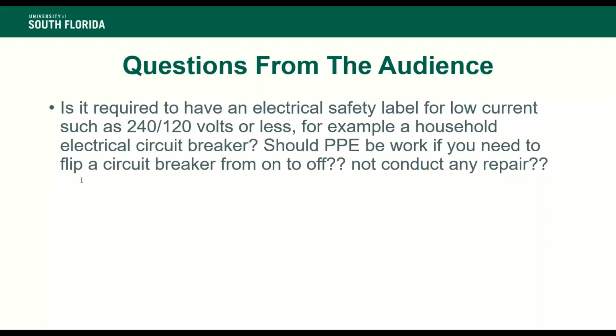If you're simply flipping a circuit breaker on and off, PPE is not necessarily required. There is a safe way to flip a circuit breaker on or off, though. Basically, you do not stand in front of it. You stand to the side where you have the least exposure should something go wrong. And again, if this is 240 or 120, it's not going to be very significant. I mean, it'll be a significant arc flash, so you would probably have to go change your clothes, but it's not going to be an earth-shattering arc flash or arc blast. And we saw within the one table where they labeled a 240, 120 or less panel in an industrial setting as requiring category 1 PPE, which is the lowest of the PPE categories.